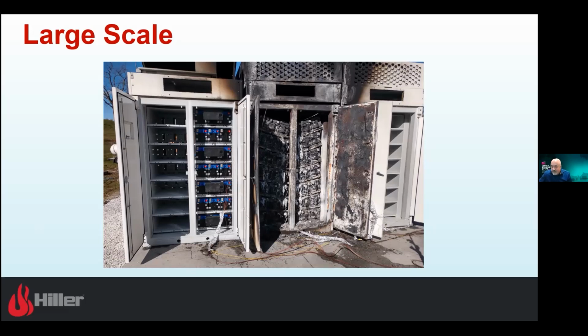Yeah, thanks Paul, I appreciate that, obviously there's quite a bit in this area. One of the things you addressed early on, I think, is a significant gap in the codes. You mentioned the three different options for meeting the explosion control requirement. One is NFPA 68, which is essentially a deflagration vent, it directs the pressure, it takes an explosion for that to actually occur. The other is prevent the explosion, NFPA 69. And the third is an engineered cabinet that, during the large scale fire test, shows that no explosions occur.